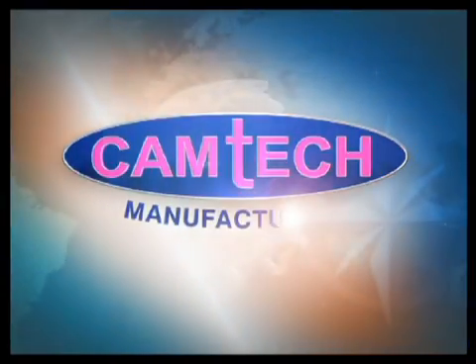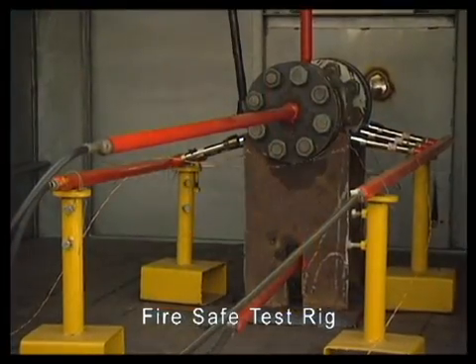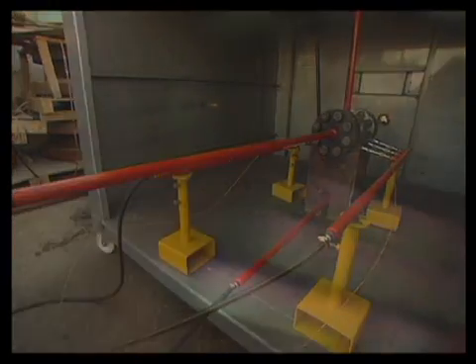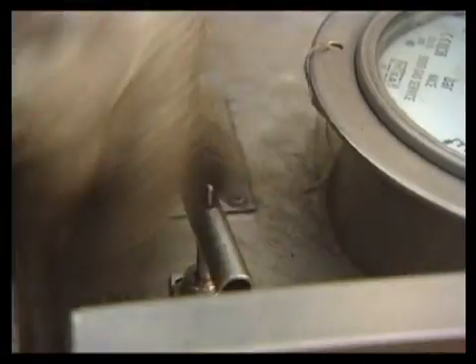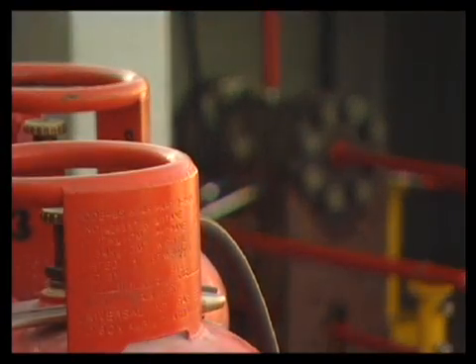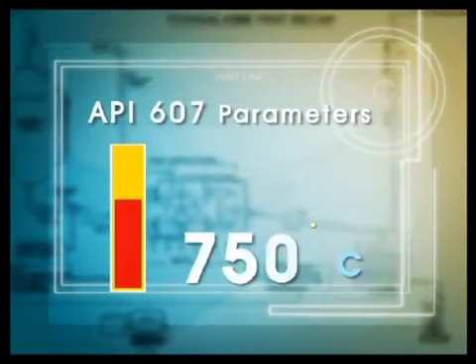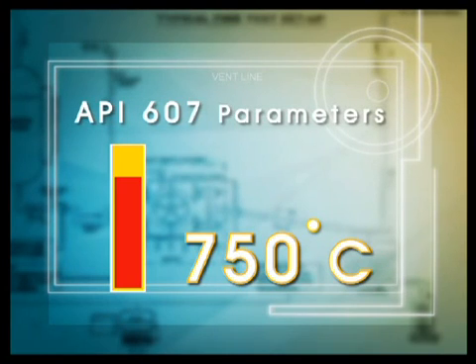CAMTECH is one of the only plants in the GCC which is equipped to carry out the fire safe test. Though every valve design prototype has to compulsorily undergo and pass the fire safe test before being put into production, this test is also carried out once again if so required by any discerning client. This test is conducted as per American Petroleum Institute's API 607 standards. The main objective of fire testing is to evaluate the leakage performance of a valve when subjected to a temperature of 750 degrees centigrade, which simulates a refinery fire within the first 30 minutes.